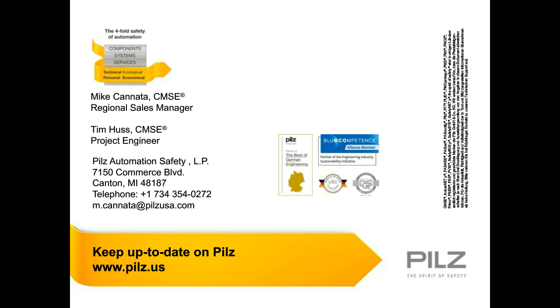Do you have enclosures for food-grade washdown environments? Yes, we have a 4X RLS box. Typically, your power panels are going to be mounted back in a non-washdown environment in your MCC room. So we don't have 4X right now, but if someone wanted them, we could put the power panels in a 4X box also. But it is a good application because you have a wet environment, and you're putting disconnects out on the floor, and you're spraying them down for washing the equipment. And so by putting the remote lockout box with 24 volts out there, that eliminates you from interacting with the higher voltages.